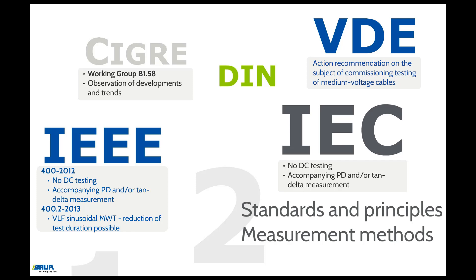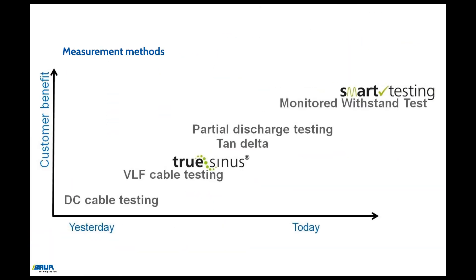We will now introduce the development of individual measurement methods. The technology in cable testing has been in continuous development over the last few decades. DC testing was used initially but has been replaced by VLF testing, which only provides information on whether the cable is okay or a fault has occurred — it provides no information about the cable's condition or remaining service life. For this reason, the simple cable test is increasingly being replaced by the monitored withstand test.